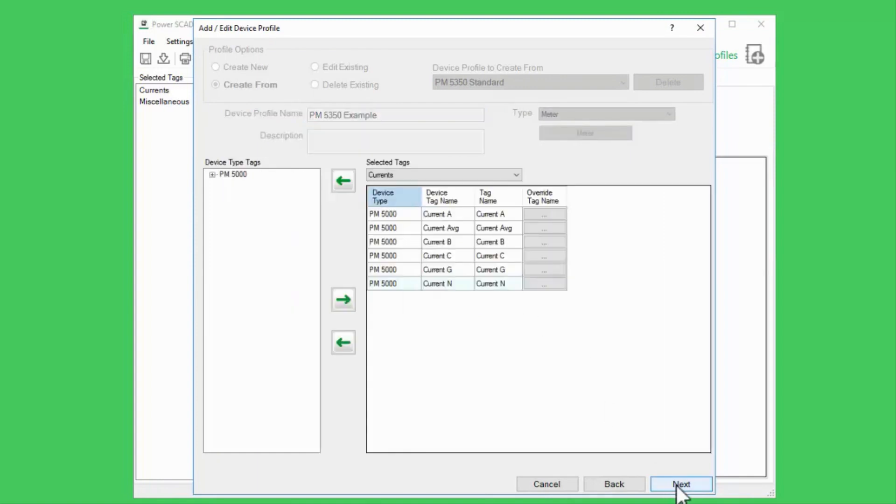Inside the alarm server, a PC-based alarm tag will take a value from a variable tag, compare it to the alarm tag's configuration, and set the alarm state accordingly.